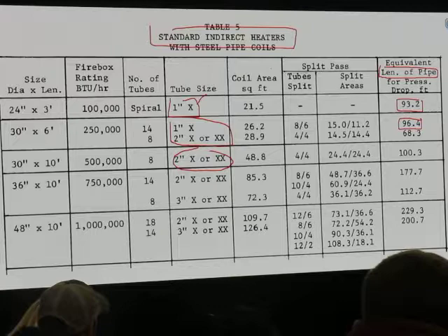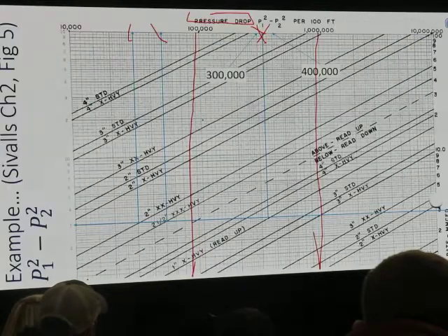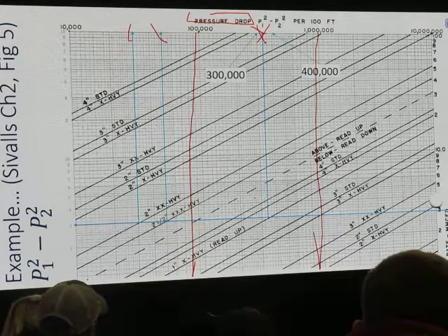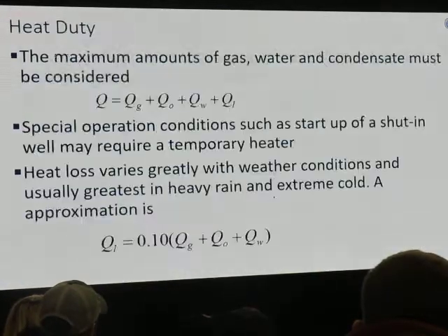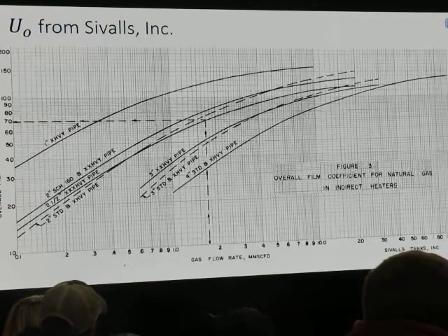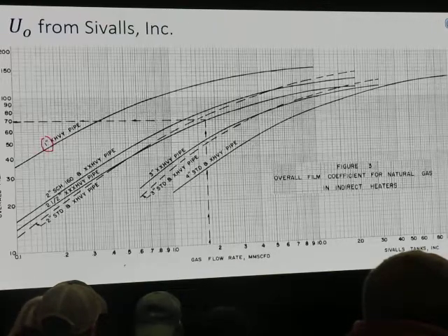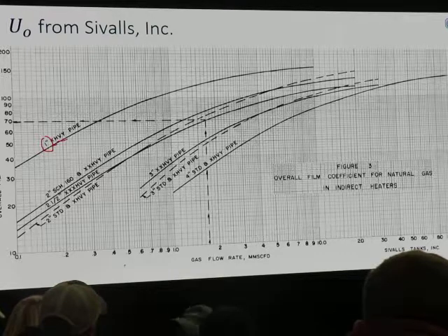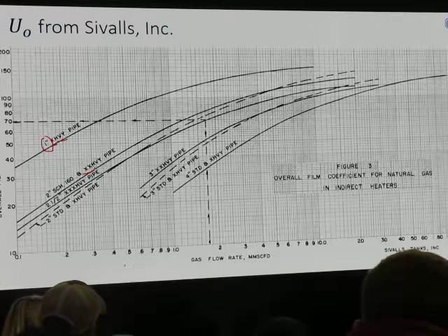So what does the X mean? Extra. So when I say extra heavy, I know that my accent may be not that great, but let's look at this chart. You see this chart? 1 inch, X heavy. So 1 inch extra heavy. If I have XX, means double extra heavy. It's bigger and getting bigger. Okay? So this X or double X is actually correlated to schedule 40, schedule 80, schedule 160.